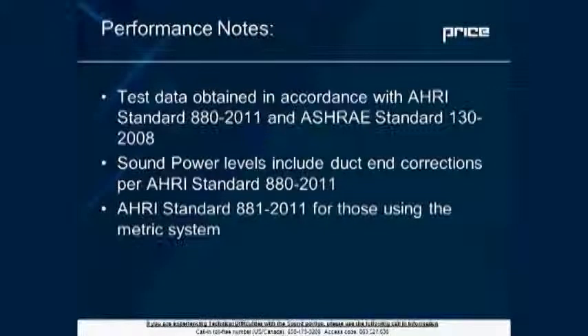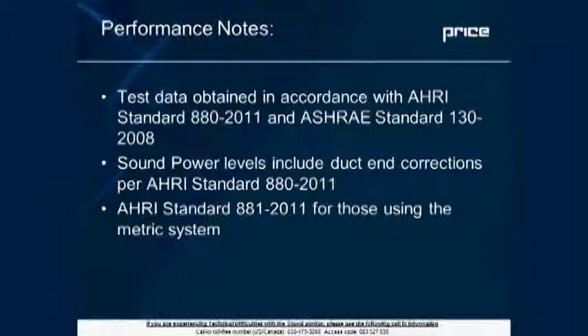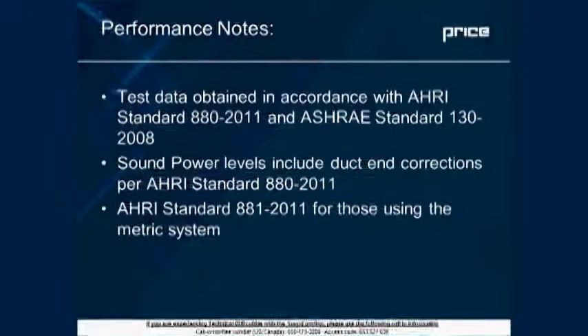In conclusion for this section, when comparing performance between manufacturers it is important to ensure an apples-to-apples comparison where discharge sound power levels include the end reflection loss. Anything published in accordance with AHRI standard 880 version 2011 would have that end reflection correction applied. With that, I'll turn the presentation over to Matthew, who will go over selection guidelines for determining which terminal unit to use for your specific project.